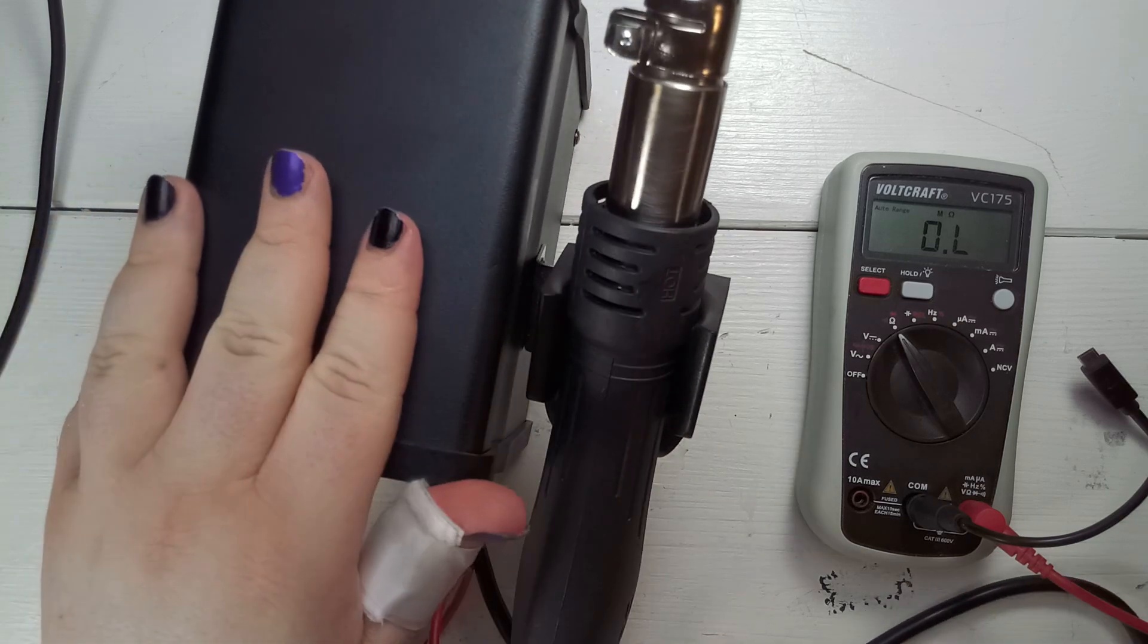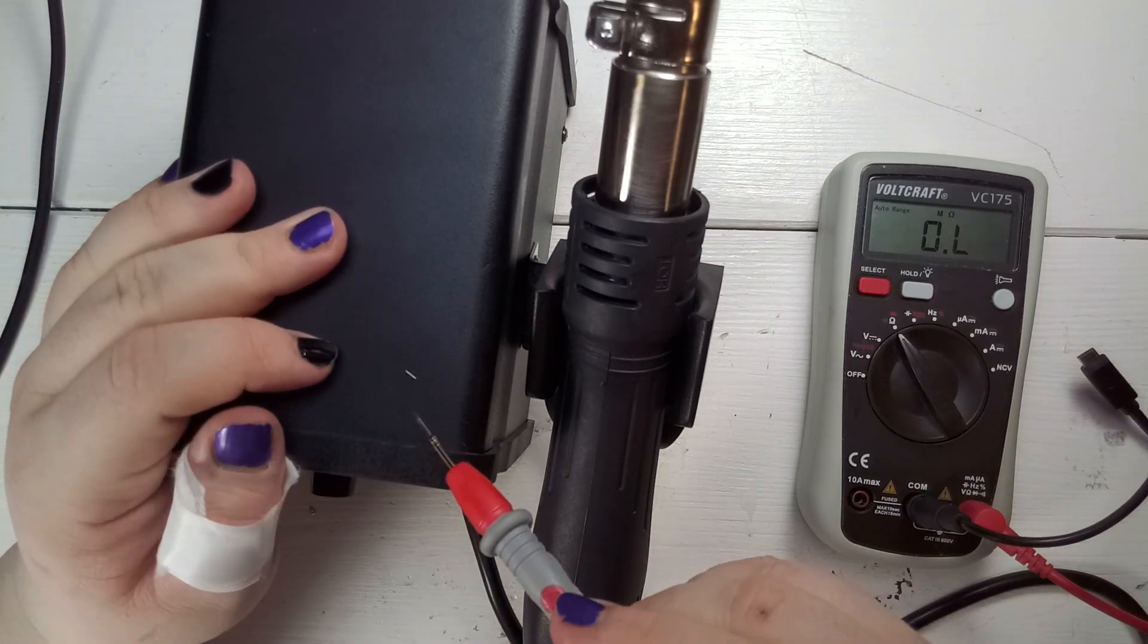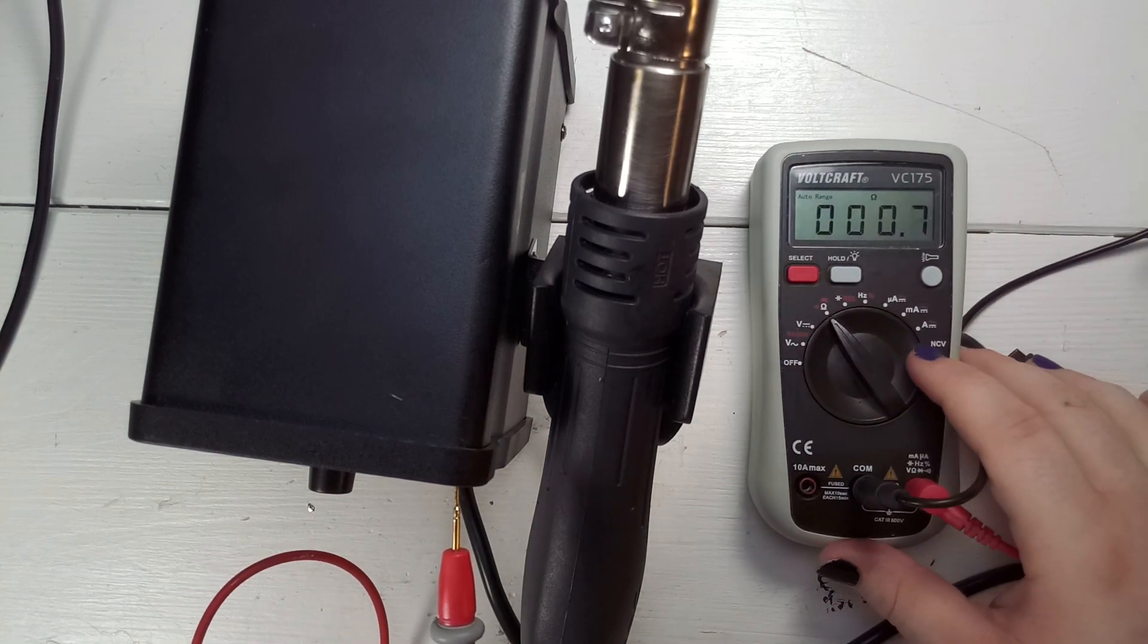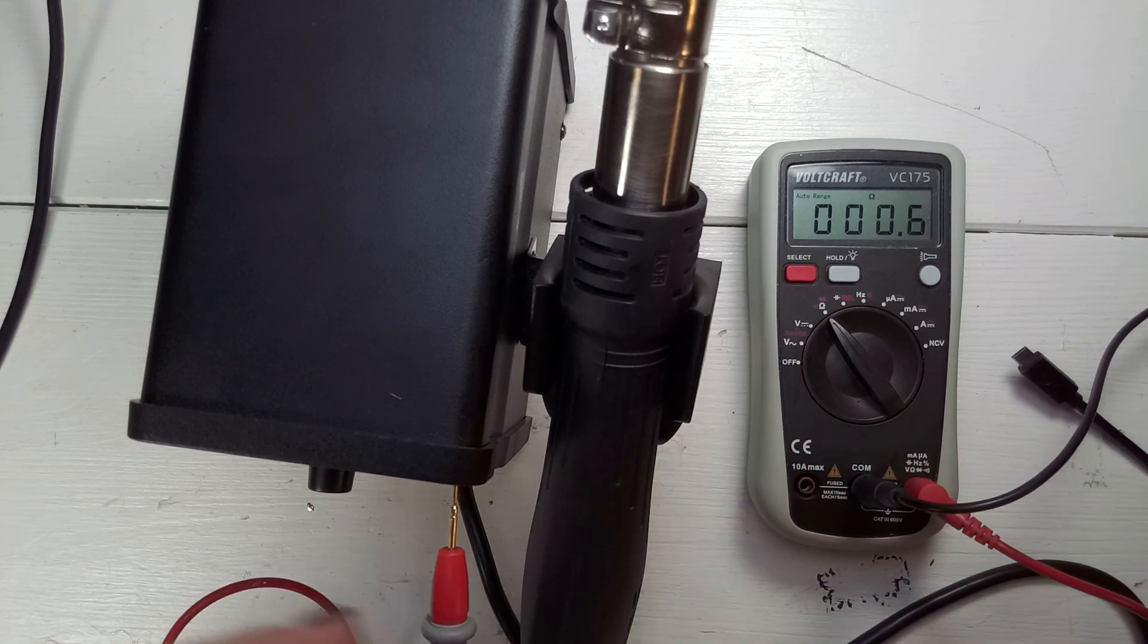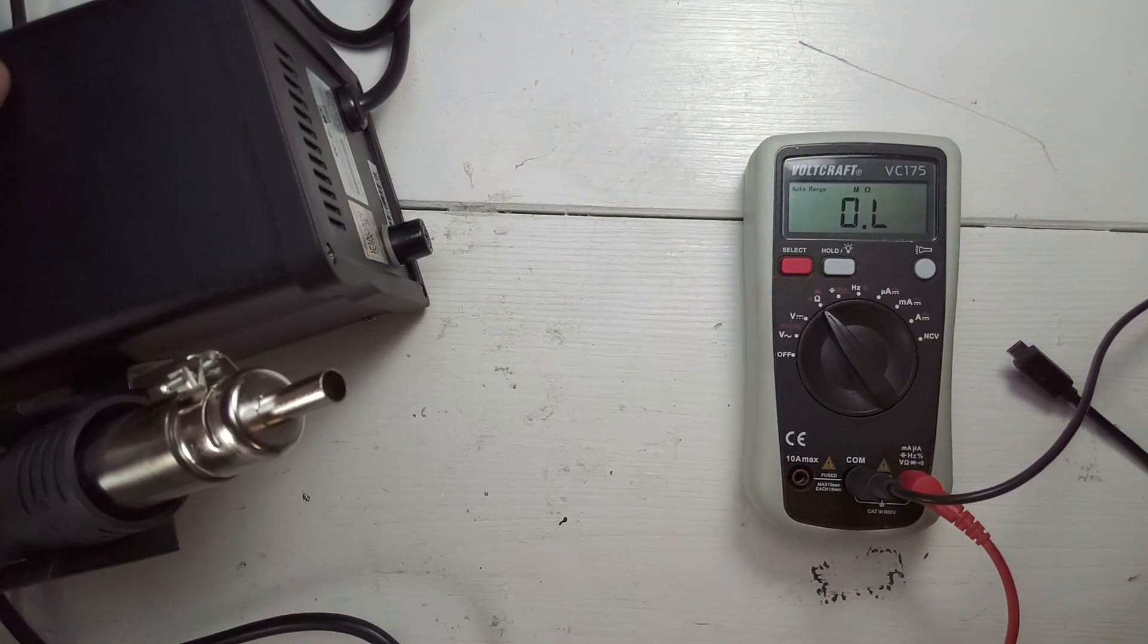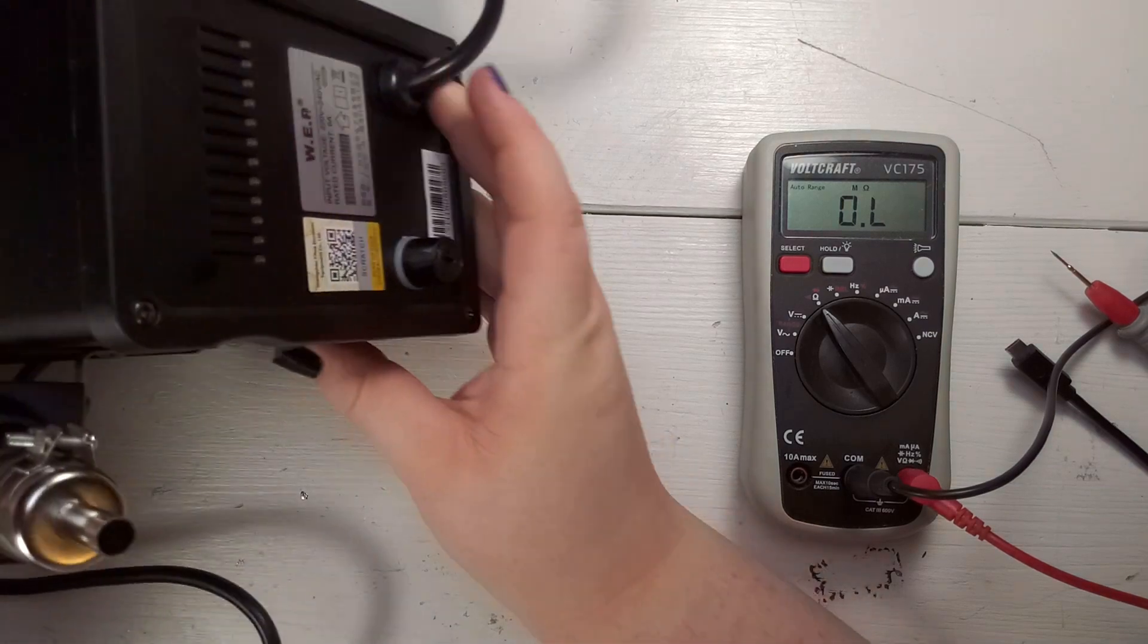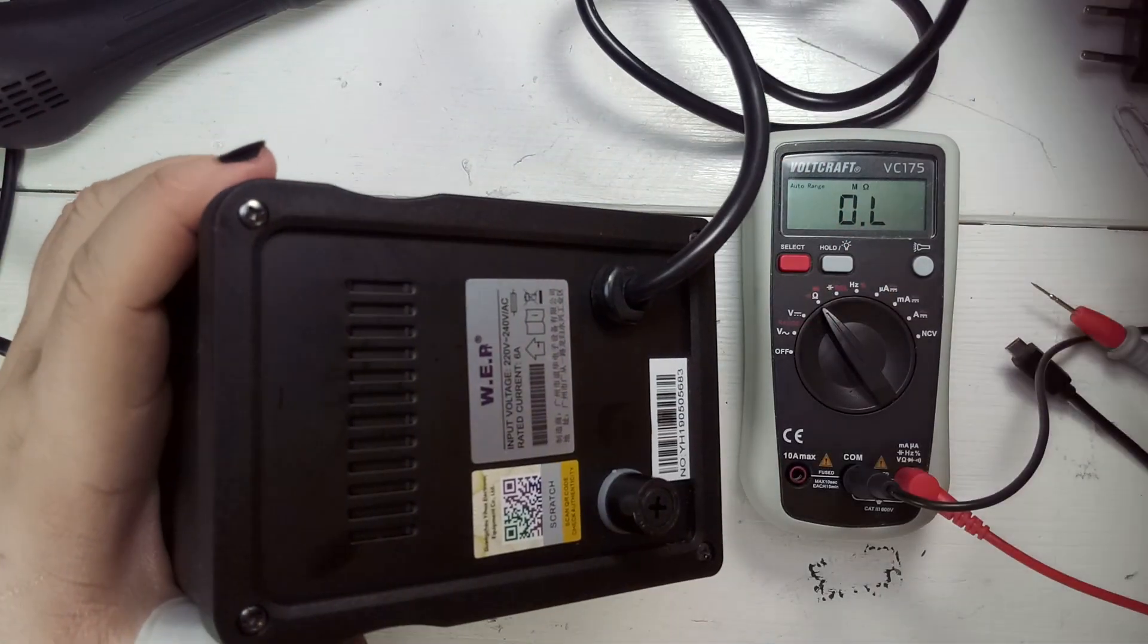So I'll use one lead that goes directly into an outlet to the protective earth prong. And this I will just touch over here. And it says we have, yeah, it's grounded. That's fine. Another thing that is also sometimes a problem, this part over here is metal. The front plate is plastic. This is most of the time not grounded. So let's see. These screws go directly into the enclosure, but it's grounded. That's nice. So this means that most of the problems that other units do have and that is proper connection to protective earth is not a problem here.